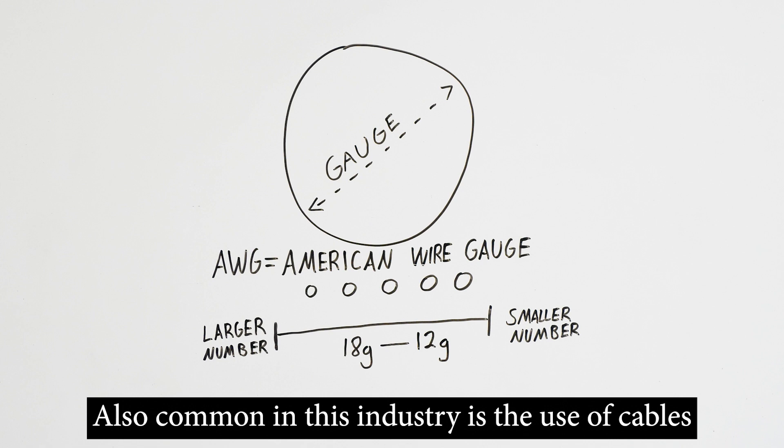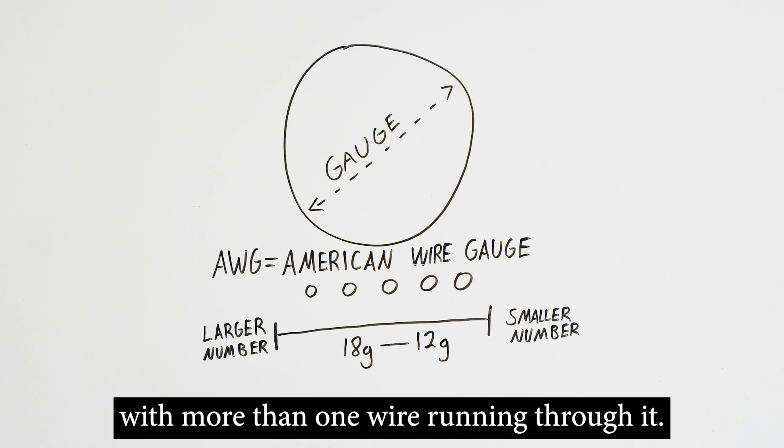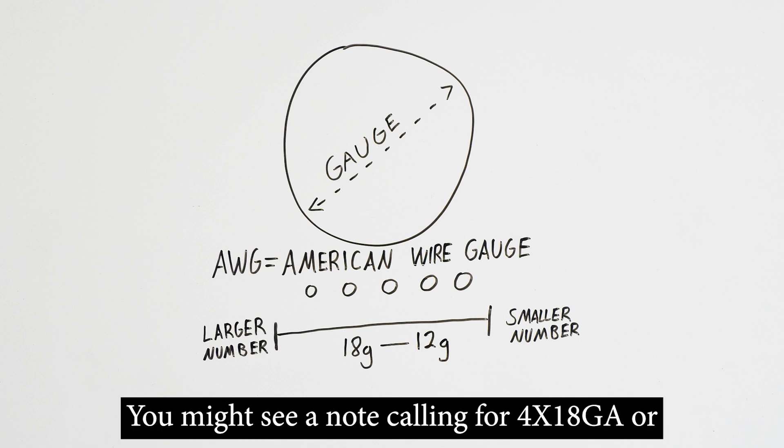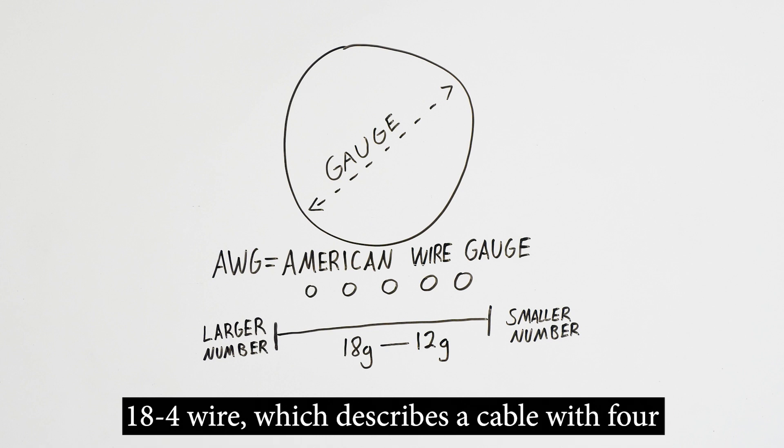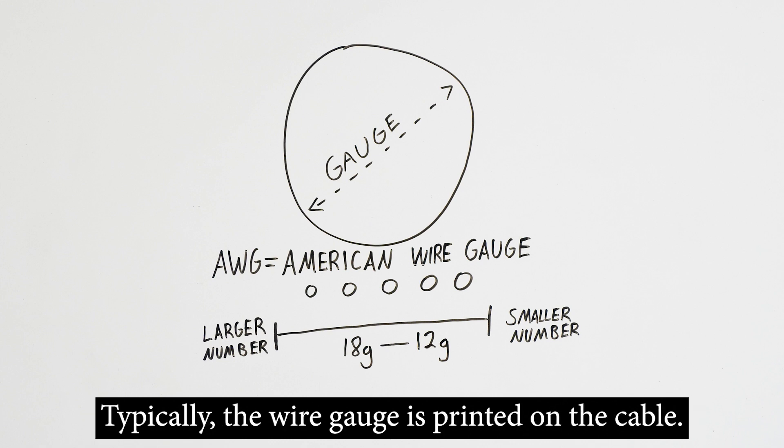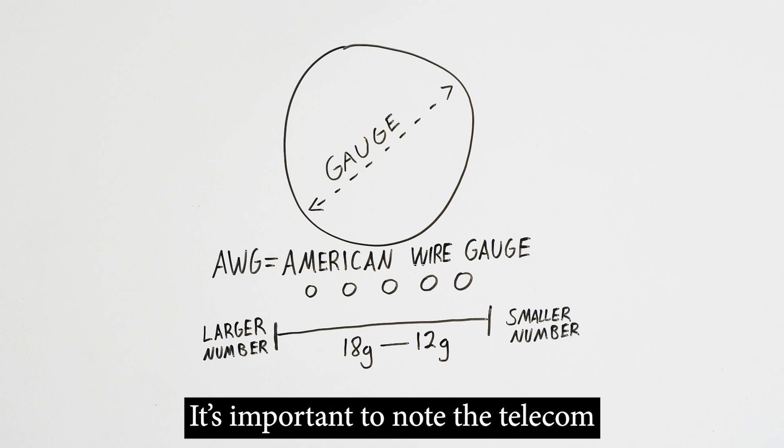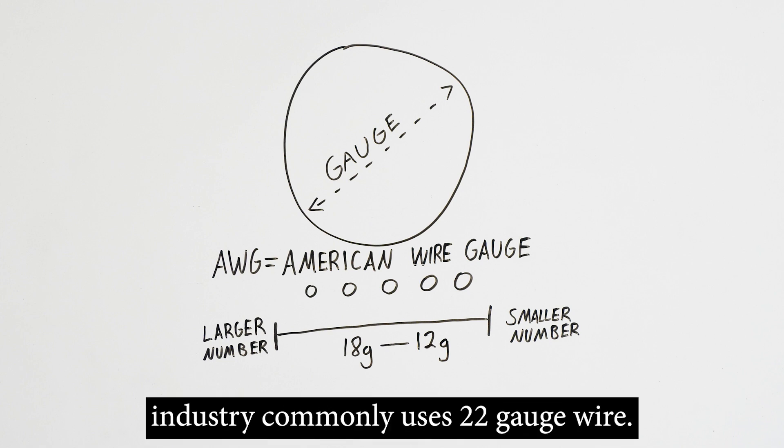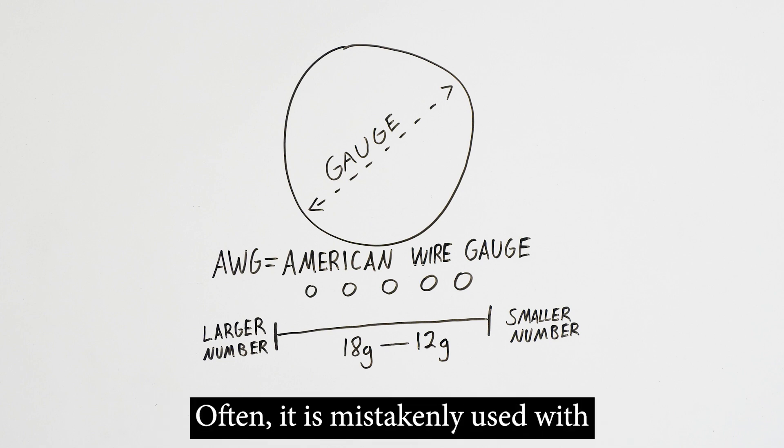Also common in this industry is the use of cables with more than one wire running through it. You might see a note calling for 4x18 gauge or 18-4 wire, which describes a cable with four separate 18 gauge conductors running through it. Typically, the wire gauge is printed on the cable. It's important to note the telecom industry commonly uses 22 gauge wire. Often, it is mistakenly used with our products, with bad results.